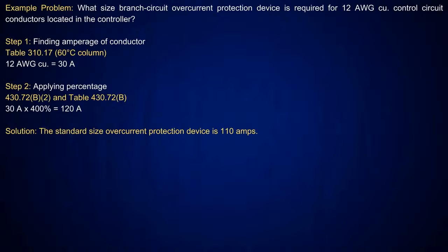The other thing I'm going to point out is that it's also going to tell you to use the 60°C column in this one. When it goes through the conduit over there, then it's going to tell you to use the 75°C column. So if I go look at table 310.17 and pick up a number 12 conductor, it's going to tell you to take it at 30 amps. All I'm doing here is checking the percentage I'm allowed for the size of the overcurrent device required for the number 12s on those control circuit conductors. It's going to tell you to take it at 400% in table 430.72(B). That's going to give you 120 amps. And I said anything over 125%, what do you do? Drop down. So the next size below that is 110 amps, and you'll see that all matches up with sizing the overcurrent protection devices.